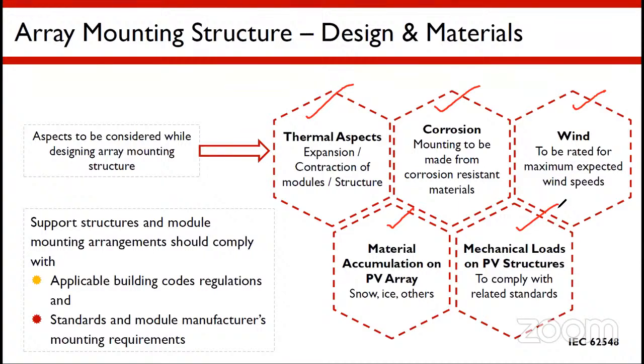If you make such an arrangement in summer, then in winter it will contract because of metal contraction during winter. So when the tension of the tightening is too high, it leads to breakage of the glass, even in thin film modules. Sometimes it happens in utility scale too, during summer, because of expansion and high tension developed in the glass surface area, causing the modules to break. Such cases have also been reported. That's why you need the correct torque level to tighten the materials, and you need to choose the proper material to suit the exact site temperature conditions.